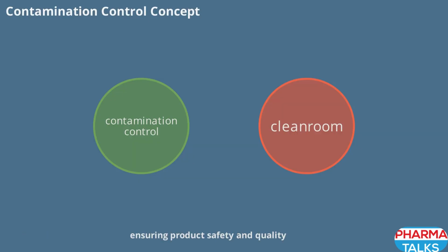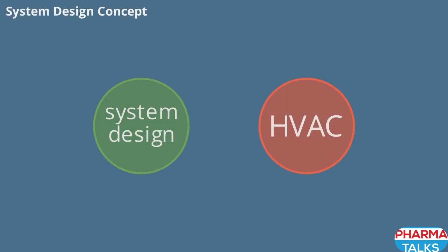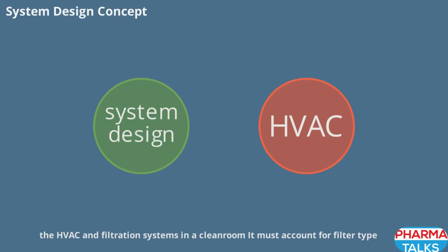Final filtration stage refers to the last filter in the HVAC system before air enters the cleanroom. This is typically a HEPA or ULPA filter, ensuring that only ultra-clean air reaches critical environments. Proper installation and validation of this stage are essential for cleanroom integrity. System design encompasses the planning and engineering of the HVAC and filtration systems in a cleanroom. It must account for filter type, pressure drop, air change rate, and energy consumption to ensure both compliance and operational efficiency.